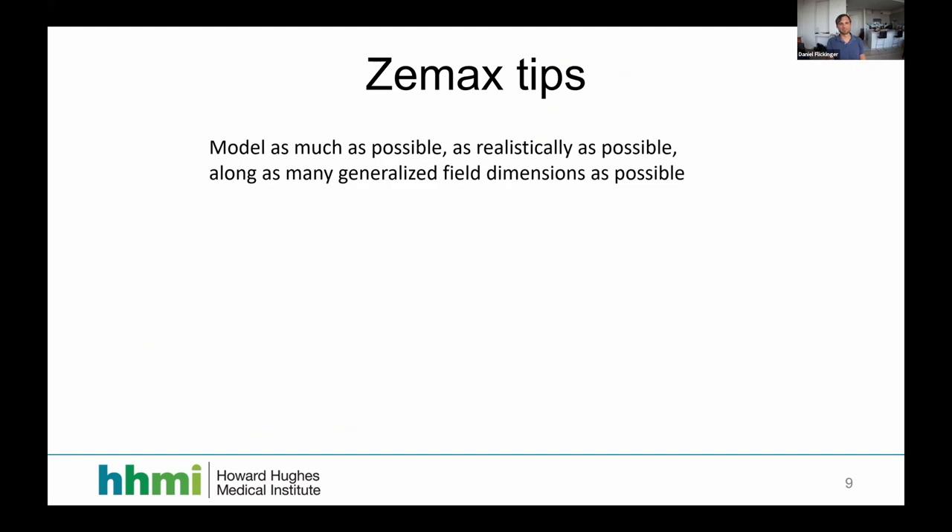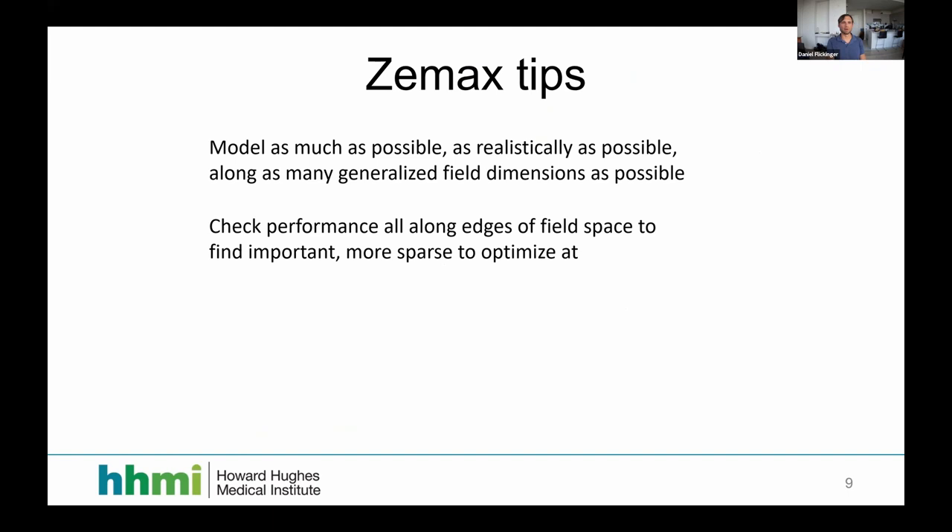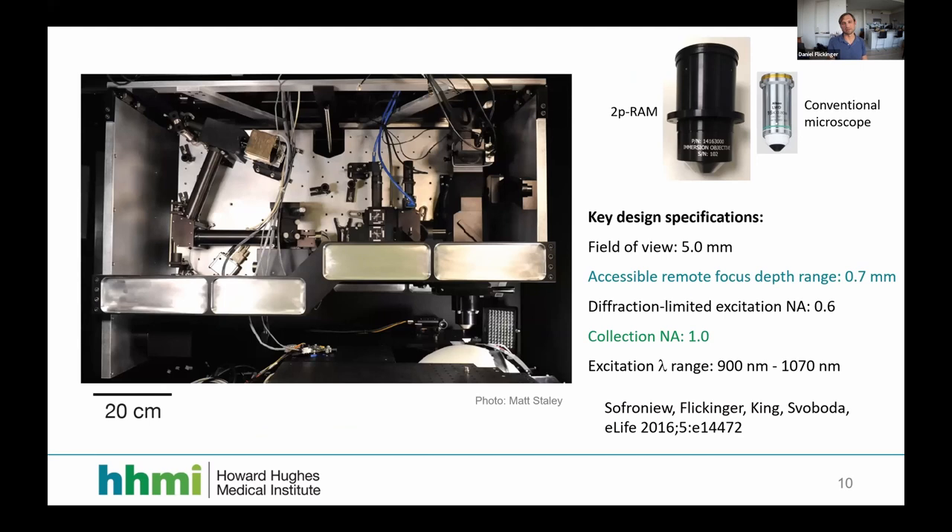Here is what the microscope looks like mechanically in real life. This large component is a voice coil actuator for the remote focus mirror. To scale, this is the Nikon 16x objective I mentioned, and this is the objective of our microscope — it is larger, because larger etendue almost always leads to larger lenses. You either make the lenses larger or increase the acceptance angle, which quickly degrades aberrations.